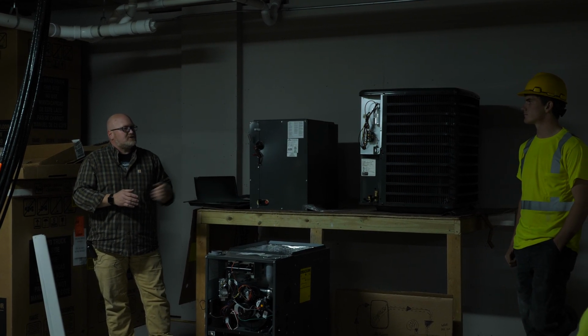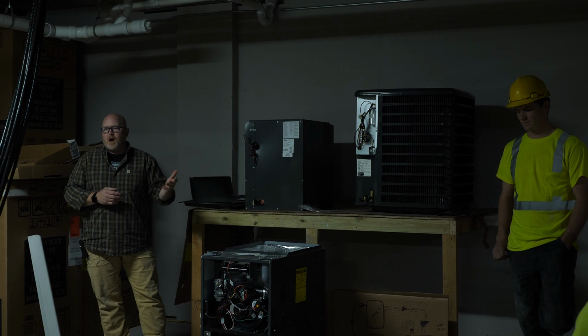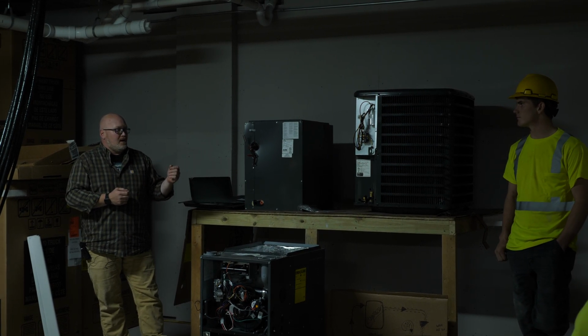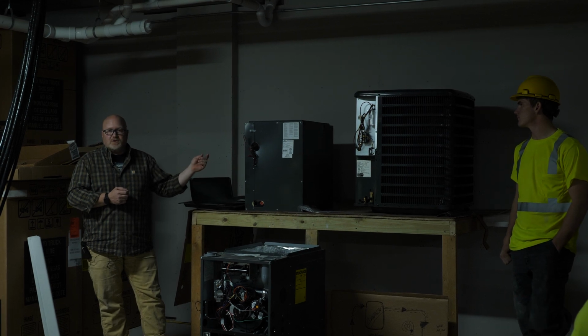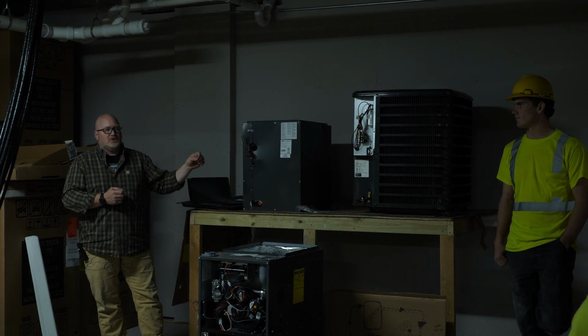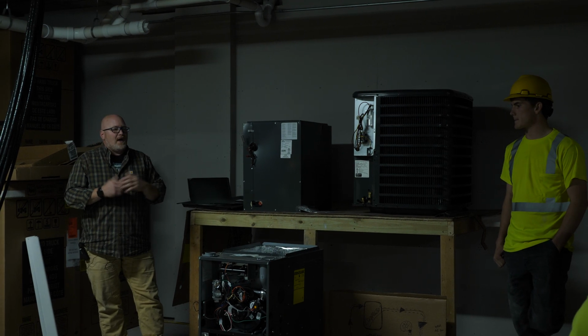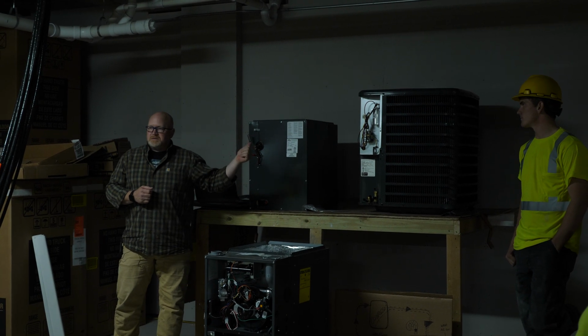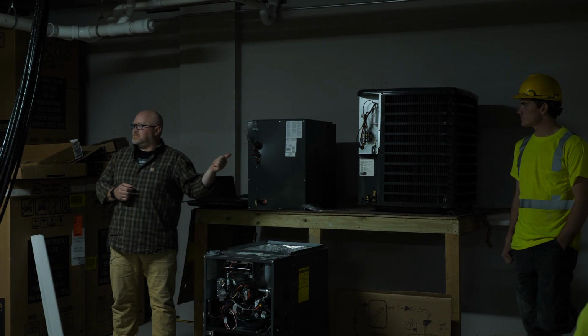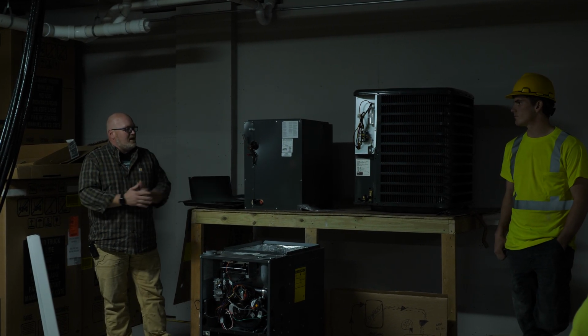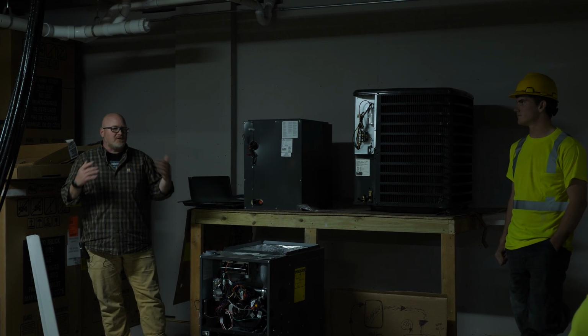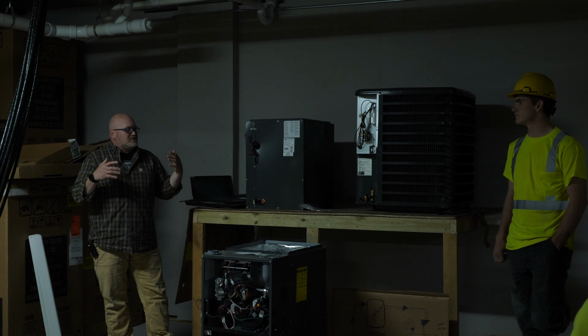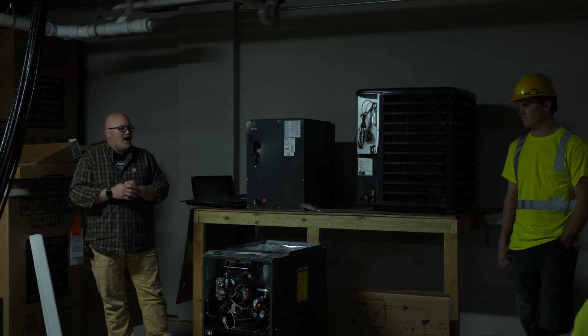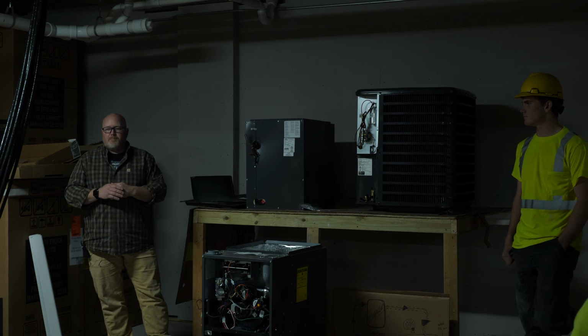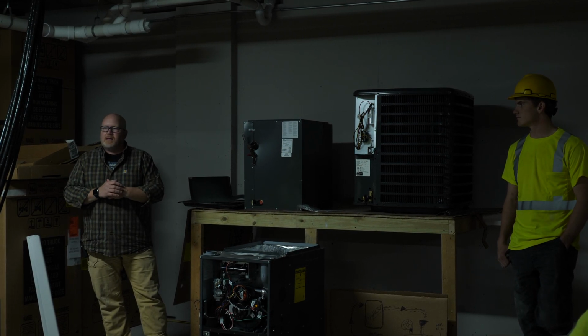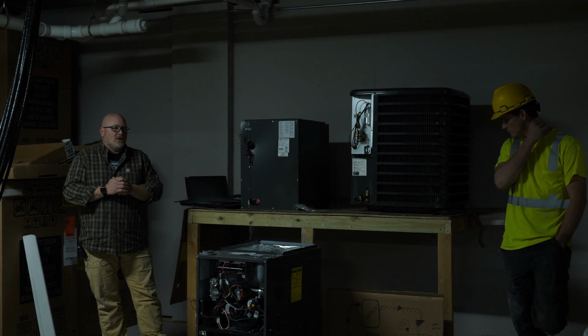And most of the equipment is smart enough now that if it's low on refrigerant, there are enough sensors and safety switches to actually shut down the system to prevent damage to the compressor. Now, with that being said, your compressor is the heart of your AC system. Everything else is boxes full of parts that can be replaced. So as we talk further about these parts, we've got a list of probably the 7 most common issues that you would have with your air conditioner. So we're going to start with those.